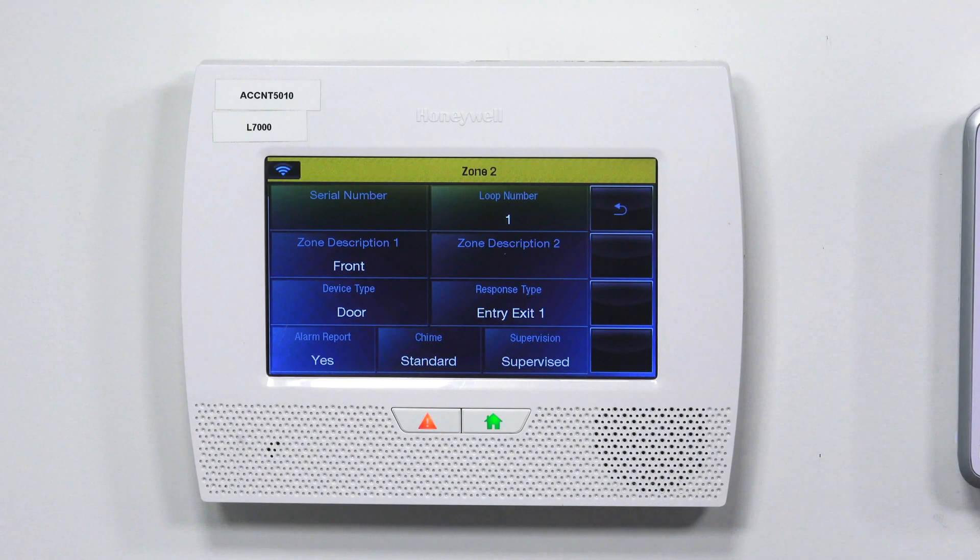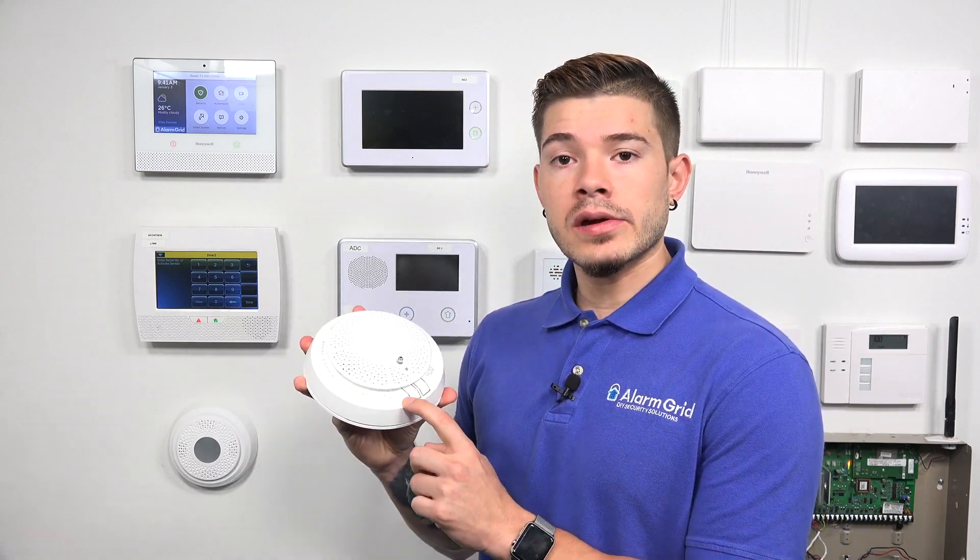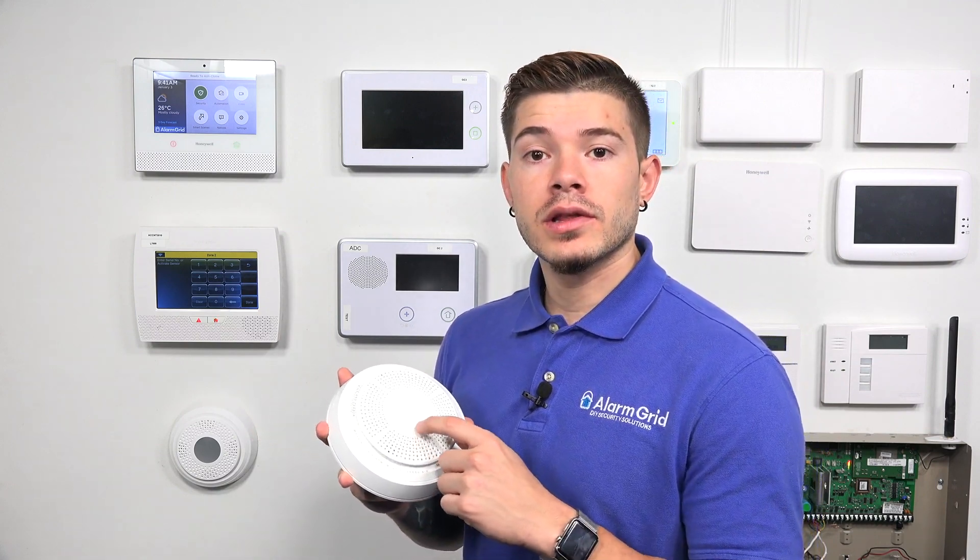Once you're there, go to Serial Number. Now that you're in the serial number field, it's going to ask you to enter the serial number for this combo detector. Most sensors, you just fault them and they'll trip. You would think that pressing these buttons would automatically learn the serial number, however, they do not — this actually starts the annunciation and test from the speaker in the combo. So instead, we're going to manually enter in the serial number that's on the back of the 5800 Combo.